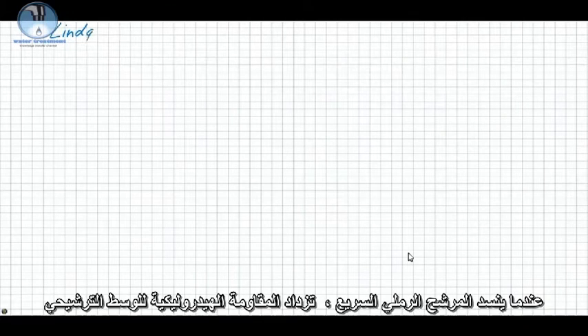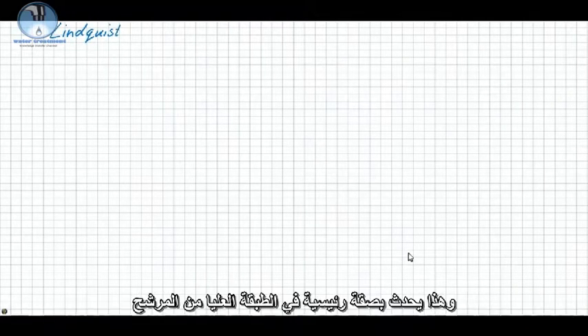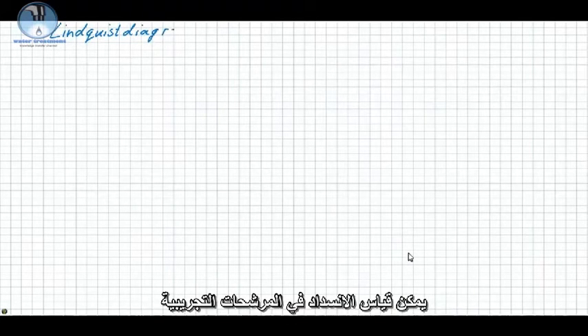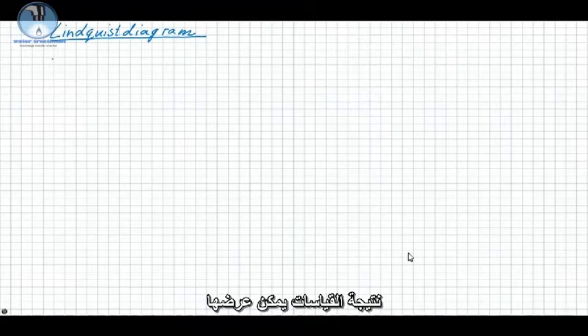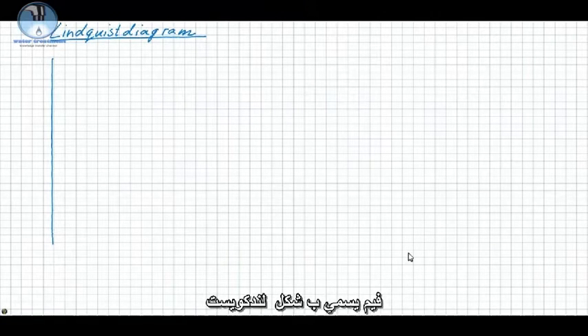When a rapid sand filter clogs, the hydraulic resistance increases. This mainly happens in the top layer of the filter bed. Clogging can be measured in a pilot filter by measuring the pressure drop over the filter bed in time. The results of the measurements can be shown in a so-called Lindquist diagram.